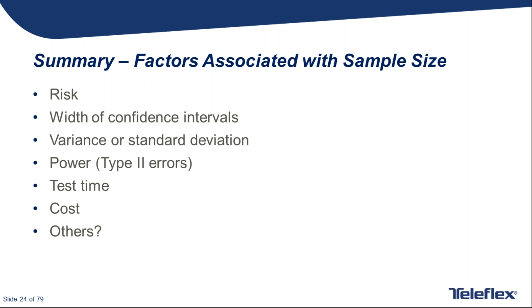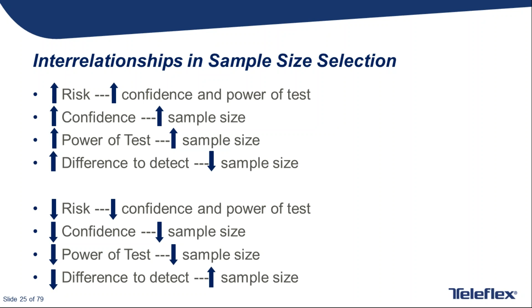Here's another way to review what's been presented so far. Higher risk drives higher required confidence, which drives larger sample sizes. Difference to detect is not as directly tied to risk. It is more of an engineering judgment or based on historical data. Now let's see how this can be applied to a specific type of testing, and I anticipate the next few slides will get into really what you signed up for this webinar for, so it gets into some specifics of application.